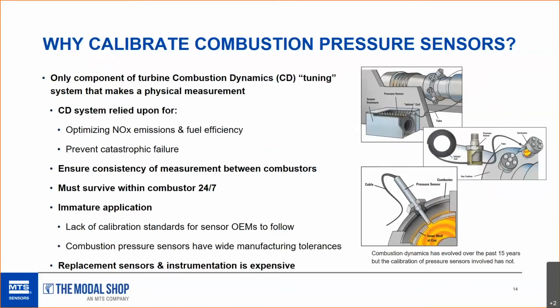So why calibrate combustion pressure sensors? Well, there are the obvious reasons shown on the slide. Combustion dynamics systems optimize the air-fuel mixture on a gas turbine, which has tremendous environmental impact, as well as contributing to the prevention of catastrophic failure. I'd like to point out something that might not be as obvious. Over the course of my career, I've watched this application evolve. Vibration is a little bit older application, but this one's relatively new.